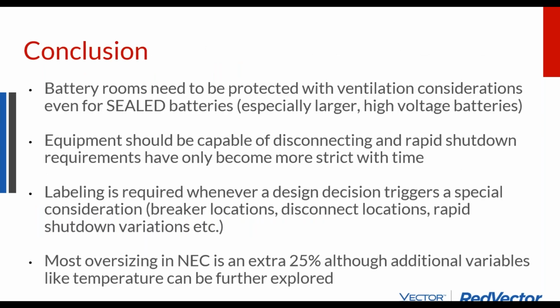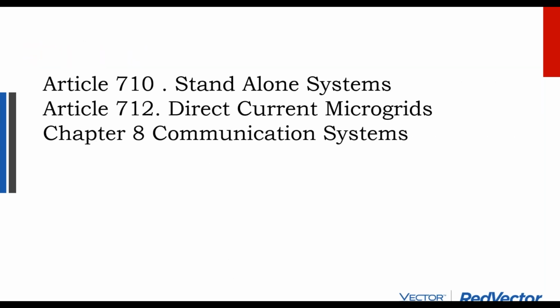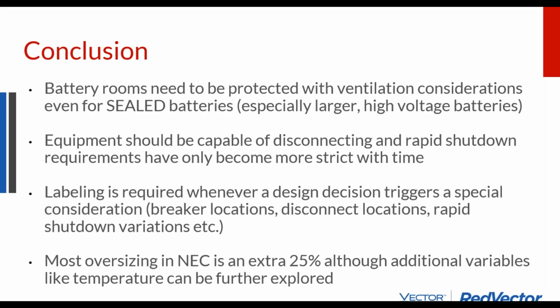And so that's kind of the end of the program. The rest of the electric code gets into fiber optic communication or microgrids, very specialty parts. The main takeaways here are that the battery rooms should be ventilated. They really should have emergency or backup ventilation so that they remain ventilated when things are going very wrong, although that's not explicitly called out in code at this time.